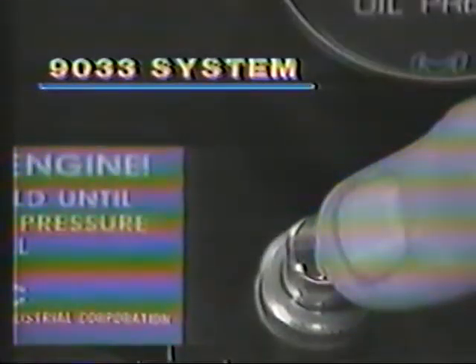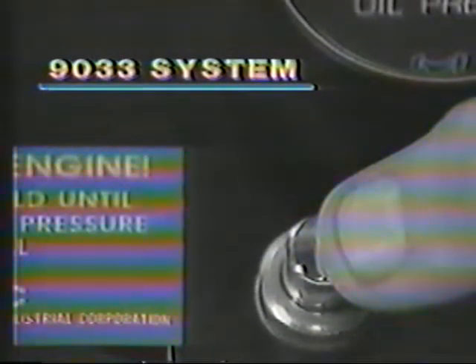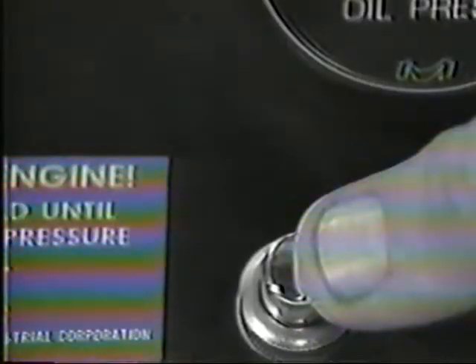The simplest override is of the manual variety, and when we add this manual push-button override to the other components, the result is a 9033 alarm and shutdown engine protection system. The override button is connected to the system fuse so that it has voltage when the key switch is turned on. To start the engine, we depress the button, which closes the switch, applying voltage to the override circuit and to the fuel shutoff.